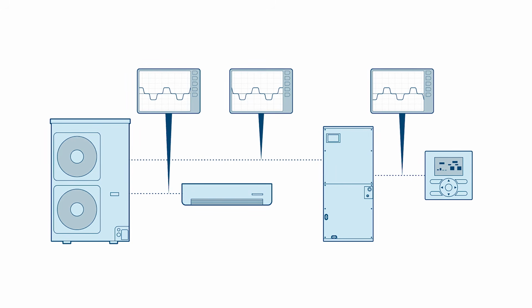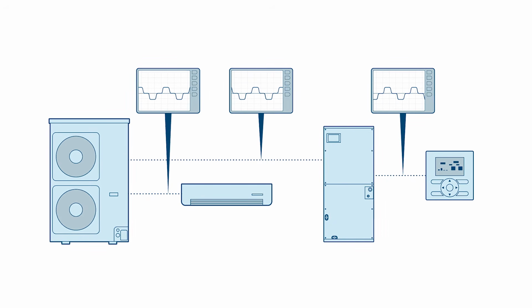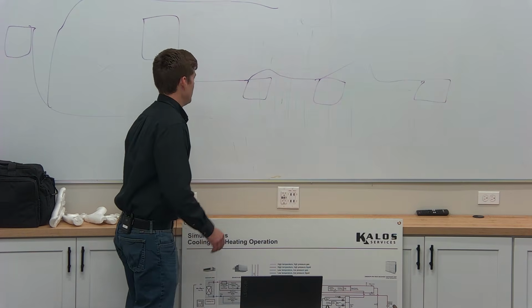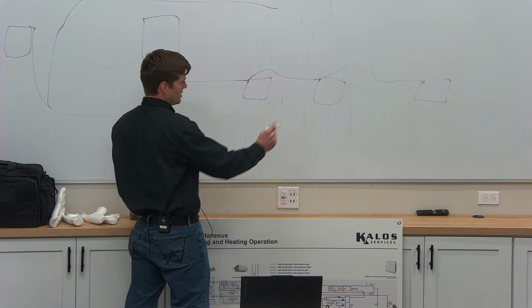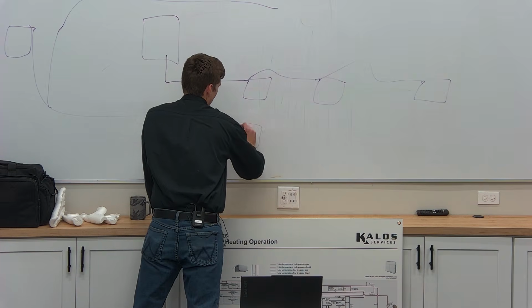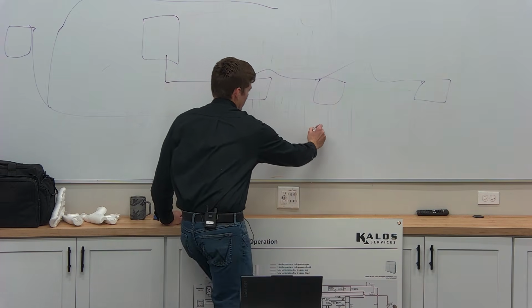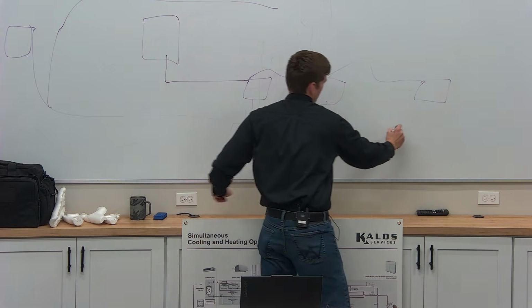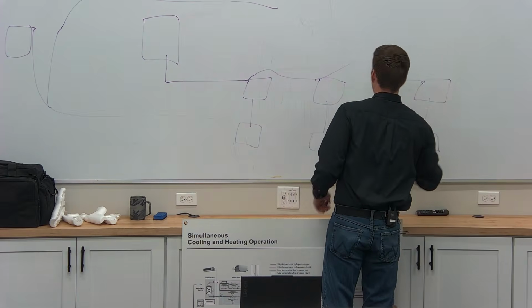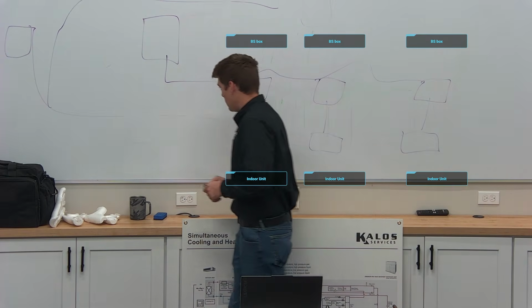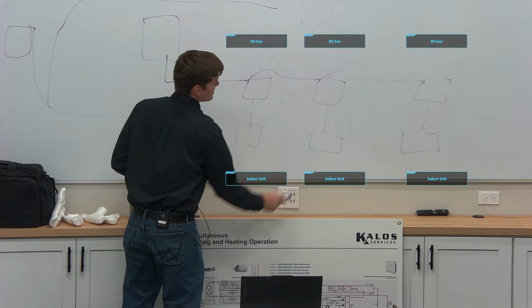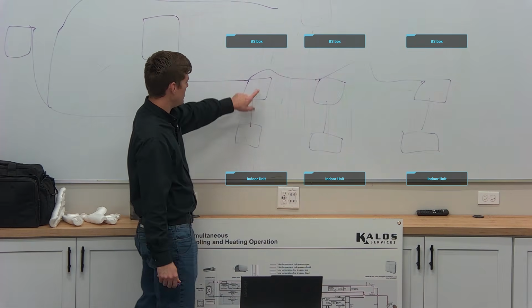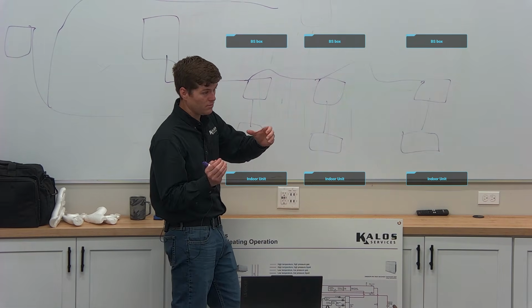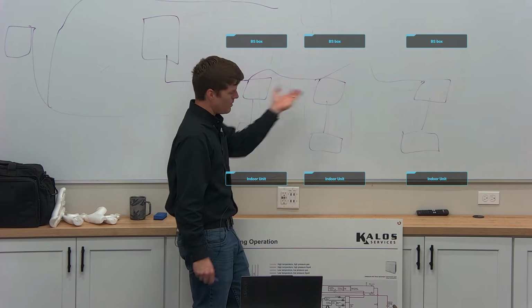On my outdoor board, I can count exactly how many indoor units it thinks it sees. On my outdoor unit, it can count exactly how many branch selector boxes it actually sees. So then if we change this layout and we add indoor units, and these are branch selector boxes, it goes like this. The big misnomer with Daikin is that this is all one big communication loop. Well, it's not really. Indoor units talk to the BS box. That's one communication loop. Then the BS box talks to everybody else on the system.